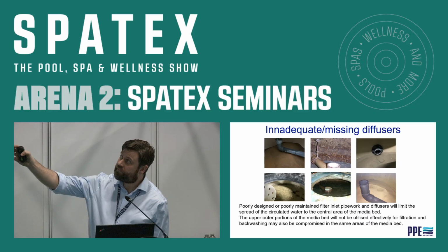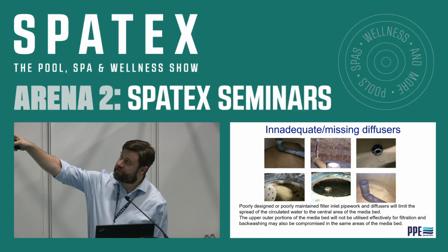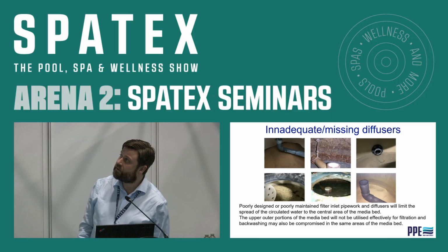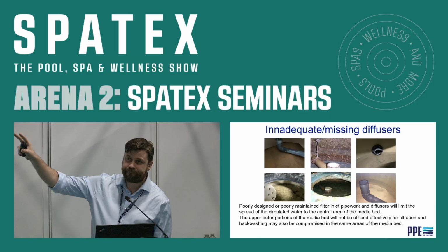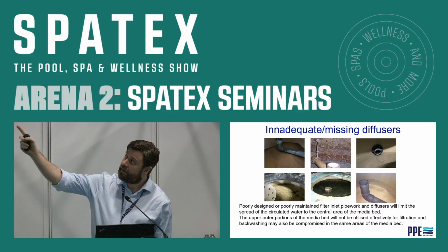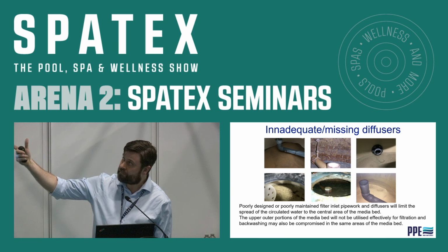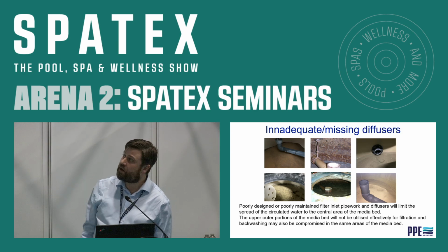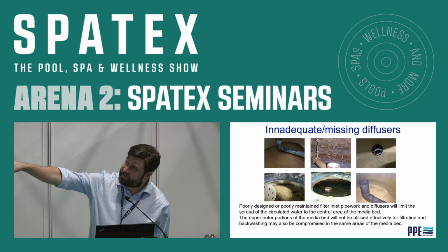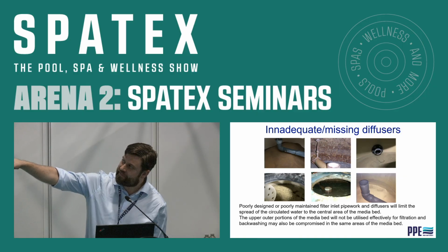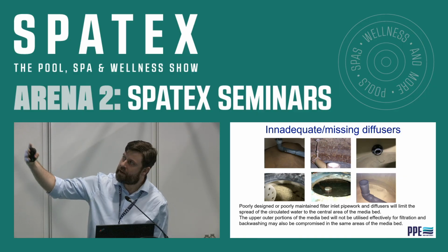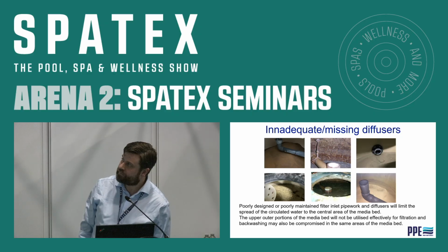Give it long enough, and this is what you're going to see. The photo in the middle, see where the media around the edges has turned more like sand and cement. The really big issues with that are going to be premature lifespan of the filter, incomplete backwashing, and therefore a lot of biofilms. Here we can see at the bottom left a lot of clumping, so we've not quite got to that stage. And this has actually got a wider diffuser, but it's still not doing enough.